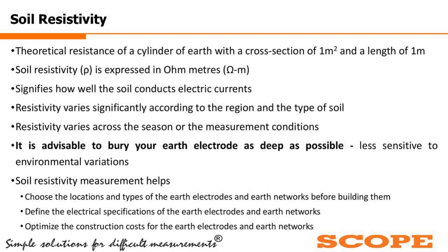So soil resistance measurement, soil resistivity measurement, earth resistance measurement seem to be very simple, but there is a very big science behind them. It is not at all a simple measurement. It requires a lot of basic fundamentals to be clear for the operator, and obviously the instrument has its own separate sets of complexities.